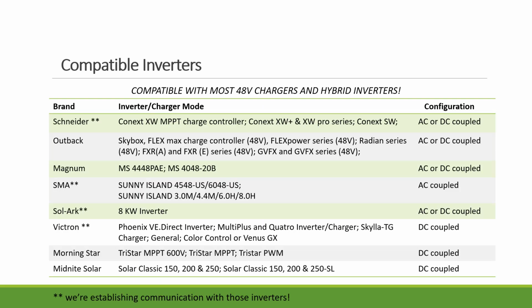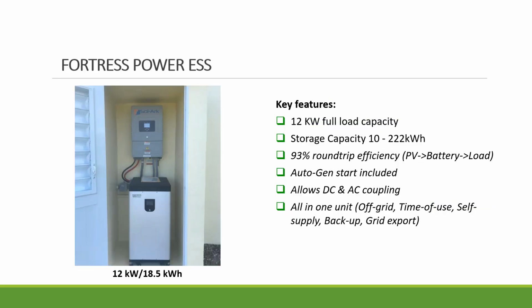Here's just a list of the inverters that we work with, and here I want to talk about the open loop and closed loop that I mentioned earlier. The open loop is that you don't have communication between the inverter and the battery, so you basically just set up the parameters in the inverter. The closed loop is that you have communication. So we are establishing communication with Schneider, SMA, Sol-Ark, and Victron. After that's been completed, the inverter will report the data to the battery and the battery will report to the inverter, and then it does not need a manual setup.